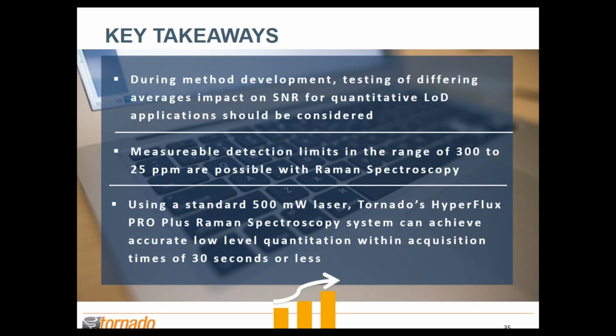Two, measurable detection limits in the range of 300 to 25 ppm are now possible with Raman spectroscopy. And they are possible using a standard 500 milliwatt laser, which means you can use the class 3 laser. And you can reach these limits within acquisition times of 30 seconds or less. This is important because somebody could look at similar limits of detection, but you need to be careful in looking at the power as well as the exposure time. I've seen other low detection studies where the reported laser power was 800 milliwatts and exposure times were 5 to 10 minutes, which lends itself to a lack of implementations for real-time online process monitoring.